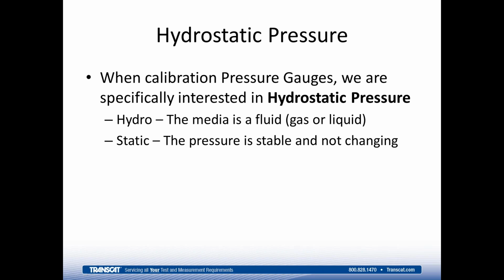Now, of course, the pressure will change during the course of our calibration, and we'll talk a little bit more about just how stable is stable. But what we're saying here is we're not looking at measuring quick spikes in pressure or the frequency of the change of pressure. Instead, we're looking at a situation in a calibration where we change the pressure, we allow it to stabilize, and then we measure it.